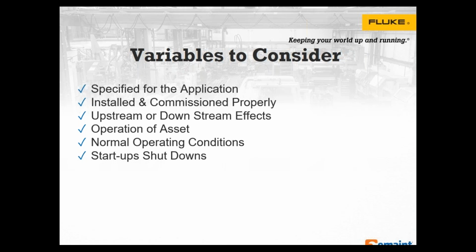And they say, oh yeah, well, we had a shutdown, and ever since it started back up, you can see a shift in the trend right there. So the first thing is, okay, what happened after the shutdown? What caused it? I can't tell you how many times I've seen issues where after a shutdown and they start up again, the asset performance has shifted for some reason or another.